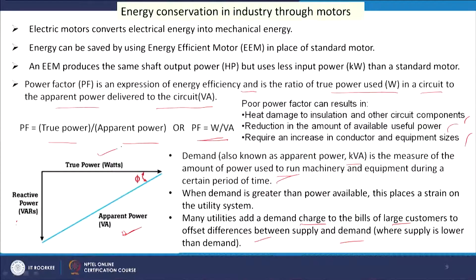We will see some numerical problems. A 60 horsepower standard AC motor is operated for 85% of the time in a year at 75% load, with efficiency and power factor of 82% and 0.8 respectively. The standard AC motor is replaced by an energy efficient motor of the same capacity at 75% load, with efficiency and power factor of 87% and 0.83 respectively. The cost of the standard AC motor and the energy efficient motor are 1,10,000 and 1,20,000 respectively. Taking the energy consumption charge as rupees 3.10 per unit and the kVA demand charge as rupees 175 per kVA per month, calculate the following if the motor operates 20 hours a day and 300 days in a year.